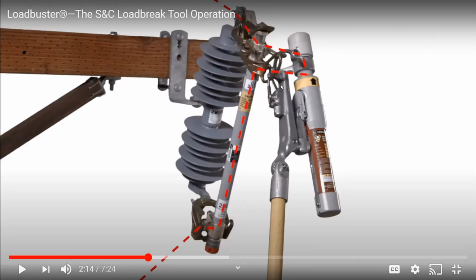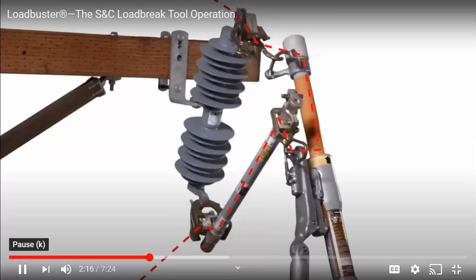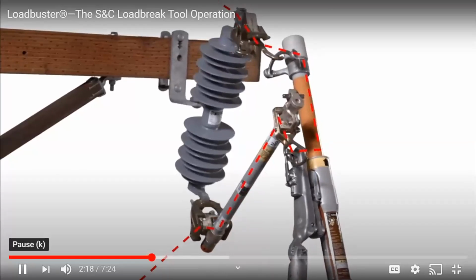As the switch stick comes down, load is busted in here and it doesn't flow from this point anymore. The top is still hot. It's because of the high side riser on top. So that was extremely fast. I would suspect they're going to slow it down here. When operated, the load current is diverted through the load buster tool.